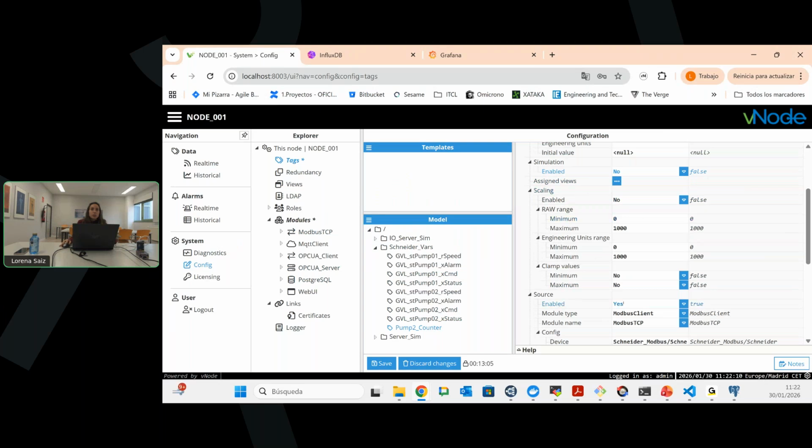Here in the scaling is where you make a pre-processing, but about the units, because not in all protocols, but in Modbus, it's really typical that to keep this protocol simple, as it works in a word register method. Imagine I want to store a temperature with 1 decimal of precision. Here in this protocol, it's really typical to put the value in one register, in a word register, but multiply by 10.